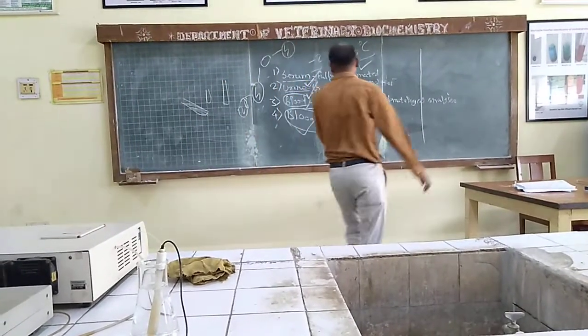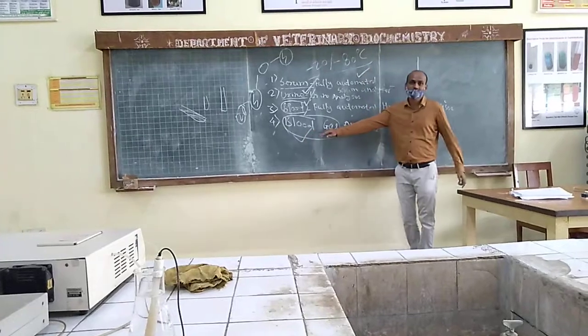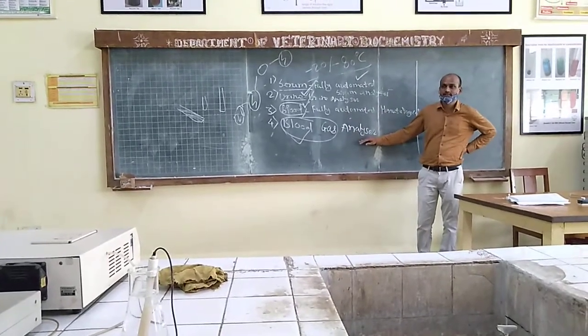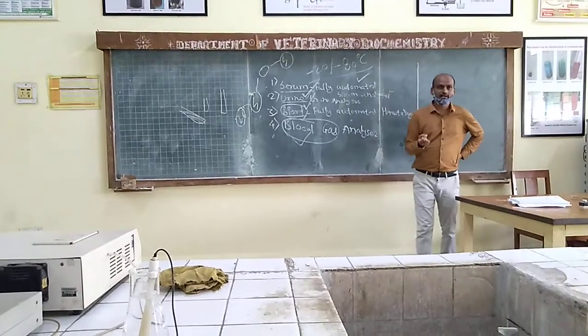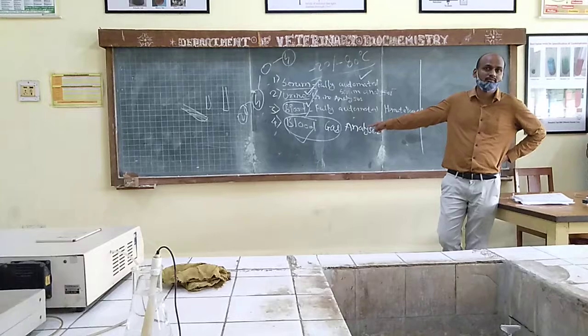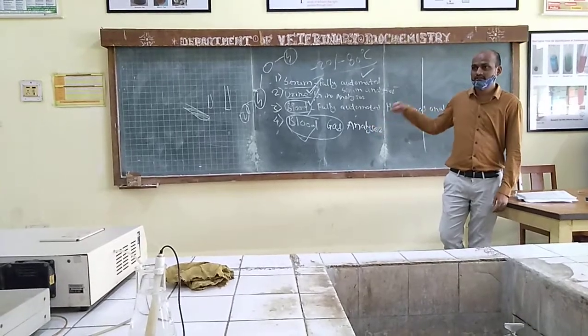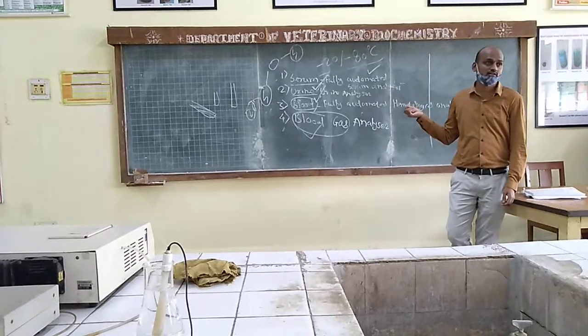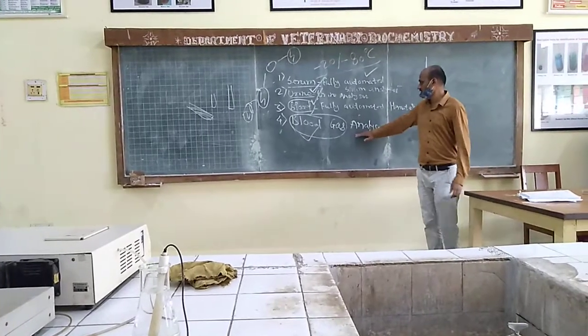Talking about instant analysis by the blood gas analyzer, whenever you are doing blood gas analysis, within 1 minute we have to show the blood to our blood gas analyzer. Otherwise, it will get clotted and this probe will get damaged. So this thing is there.